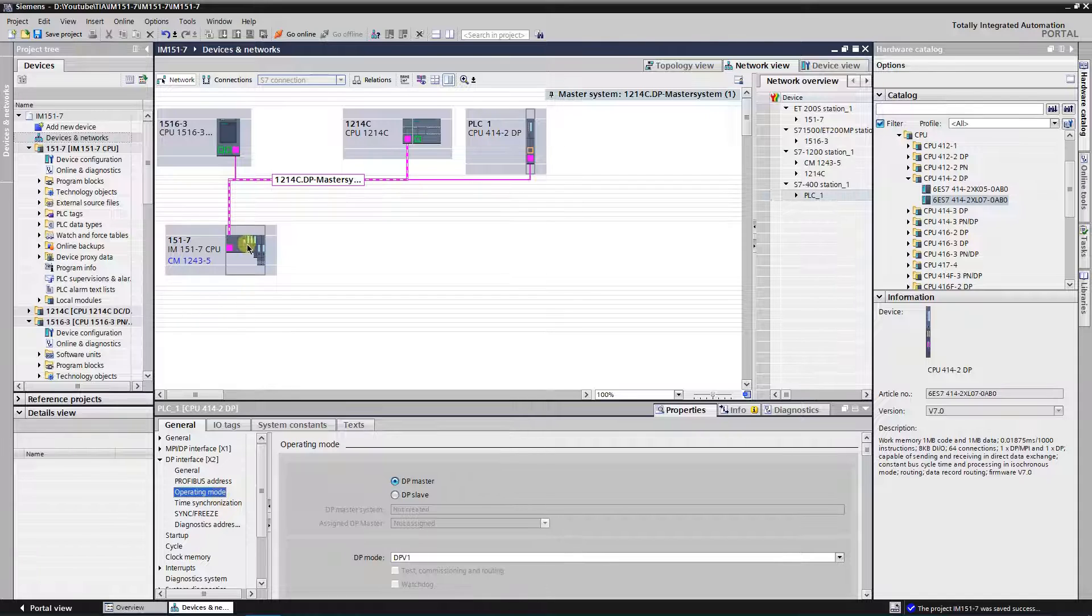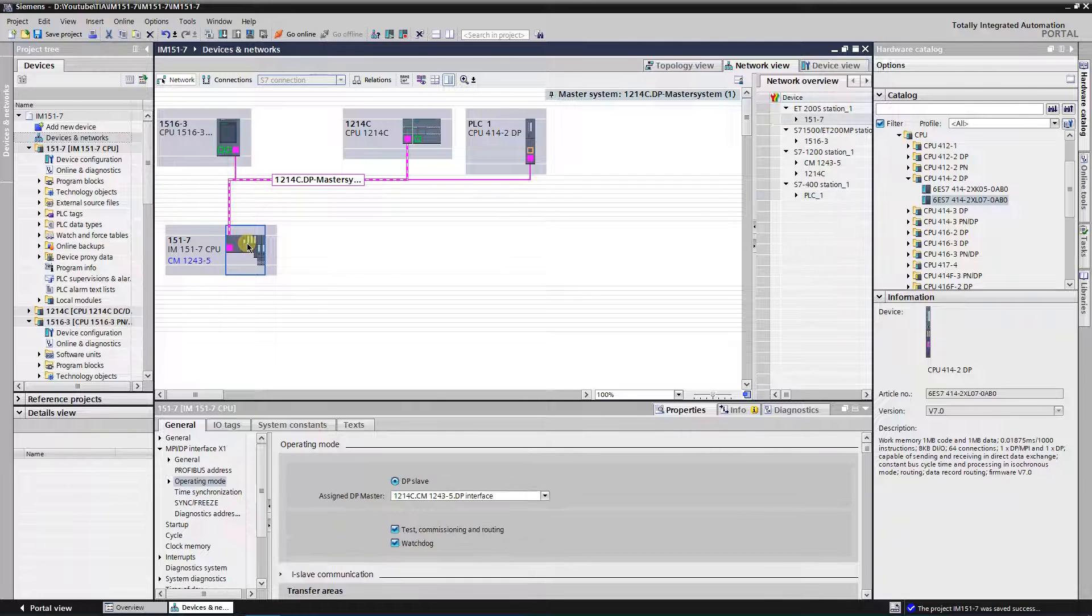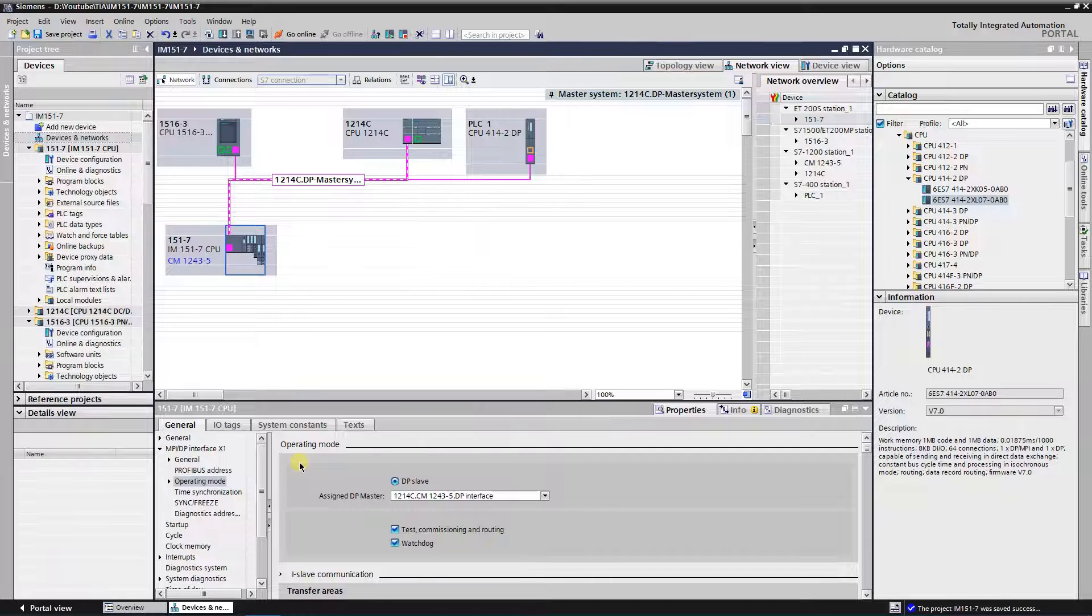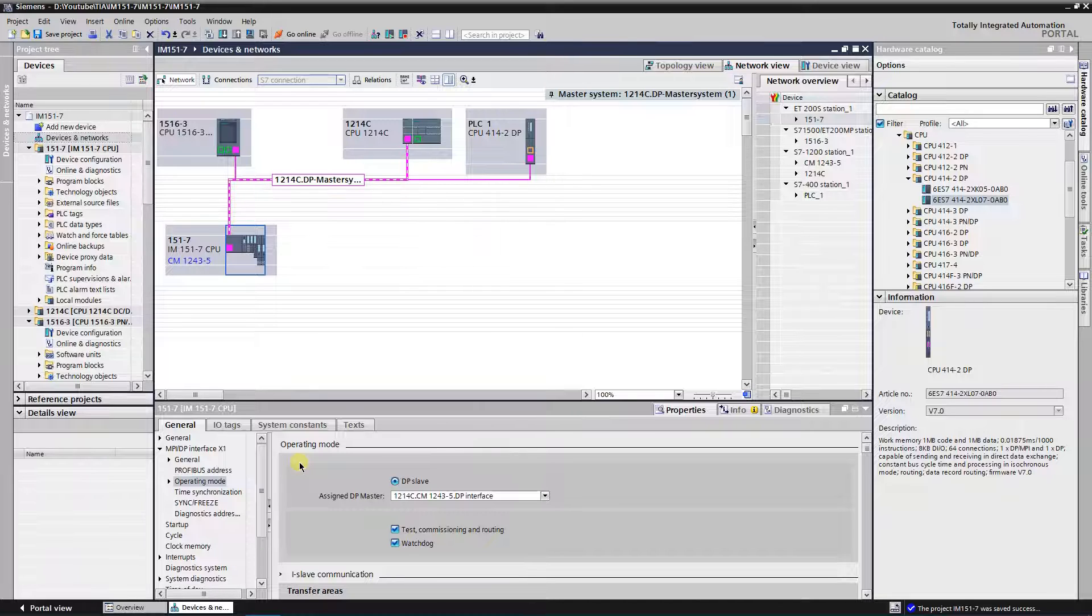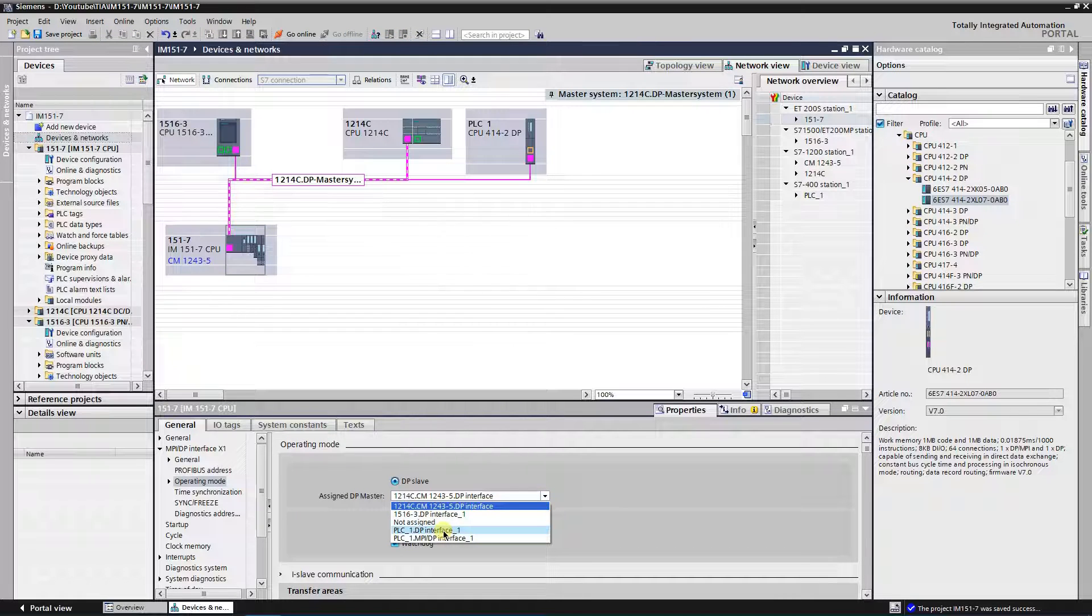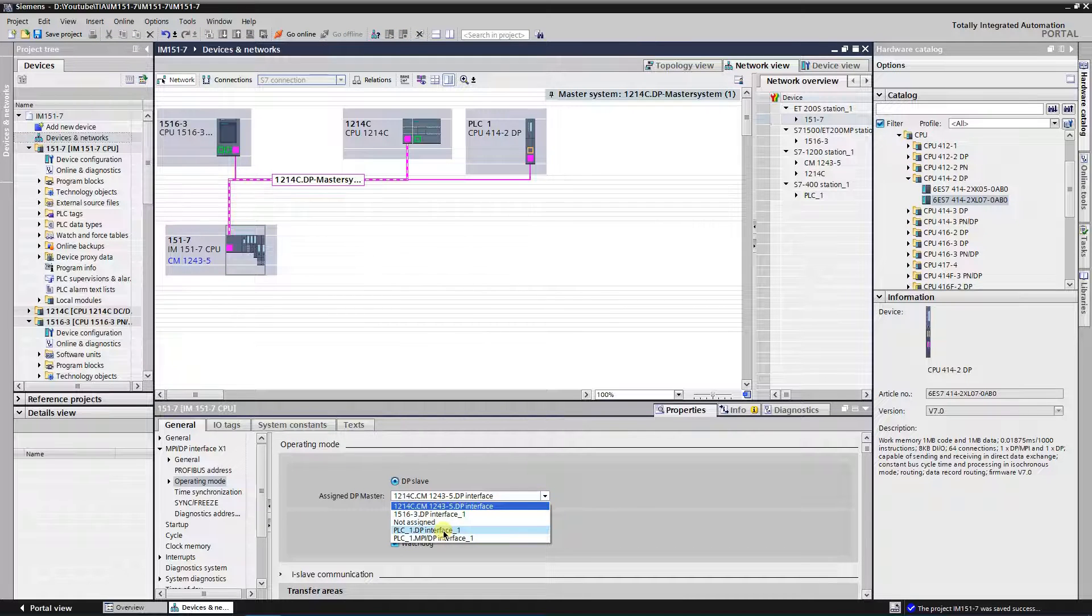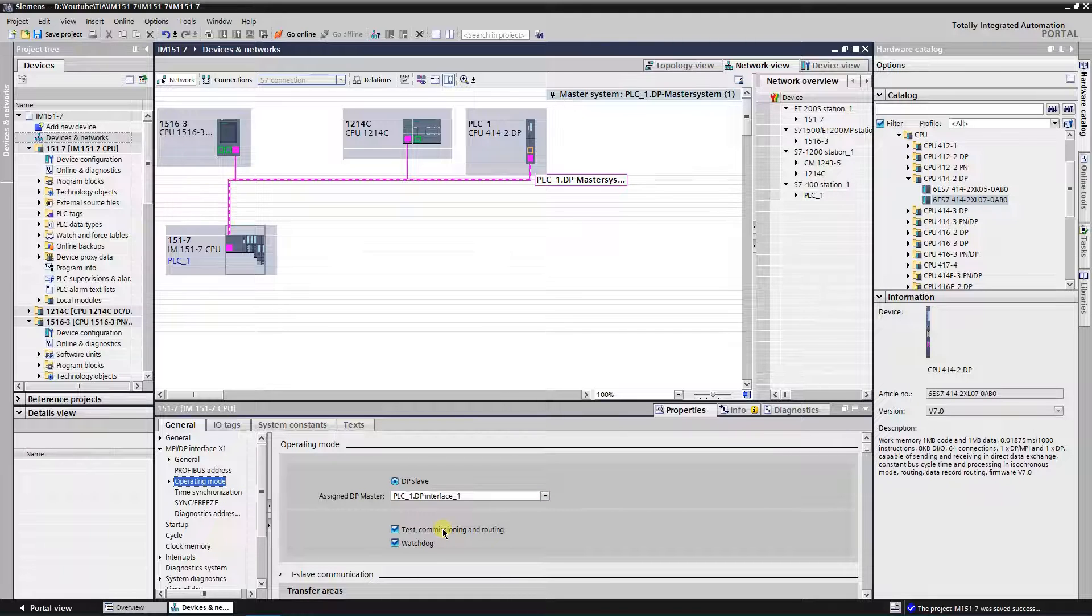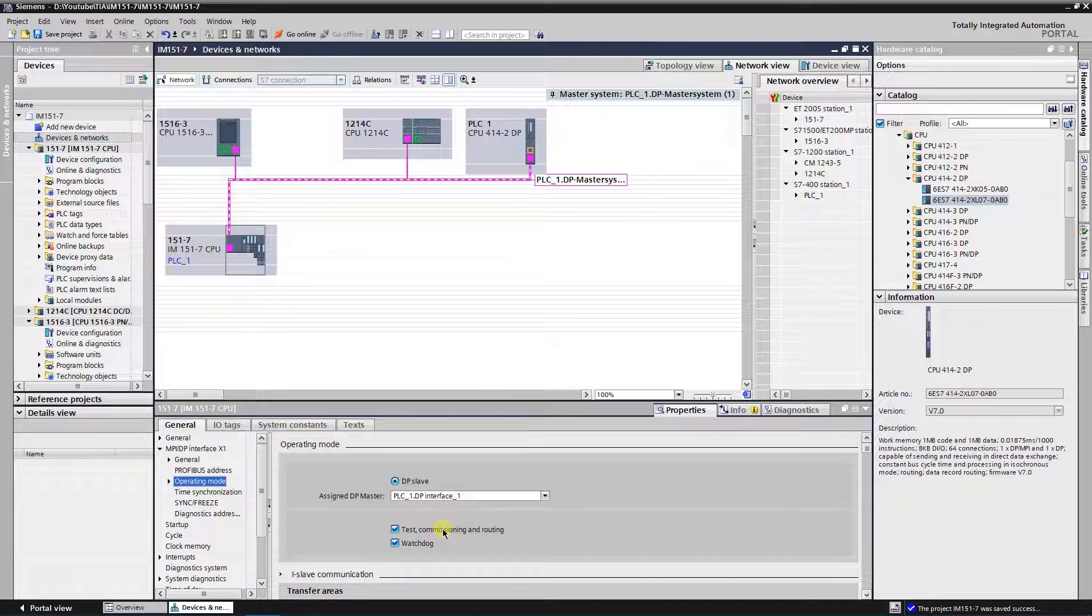Select IM 151-7 CPU. Switch to the properties, general table, MPIDP interface, operating mode. Currently, S7 1214C is assigned as master for IM 151-7 CPU. Expand drop down list, and select PLC1 DP interface as DP master. As you can see, IM 151-7 CPU became an i slave of PLC1 master system. It is an i slave of S7 400 PLC.